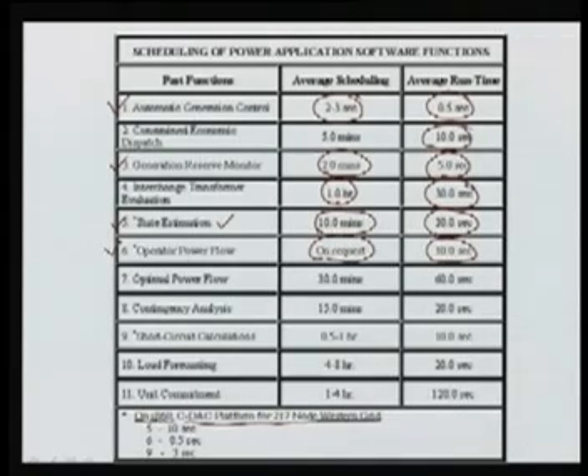Here again, in the operator's power flow, there are two types of power flow. One is offline, another is online. Online power flow is normally performed in the contingency analysis process. However, offline is whenever required, you can do this study. So it is 10 seconds if it is a big system. This optimal power flow is also known as economic load dispatch, and it requires 60 seconds. It depends again on the system. If your system is very large, its time may increase.